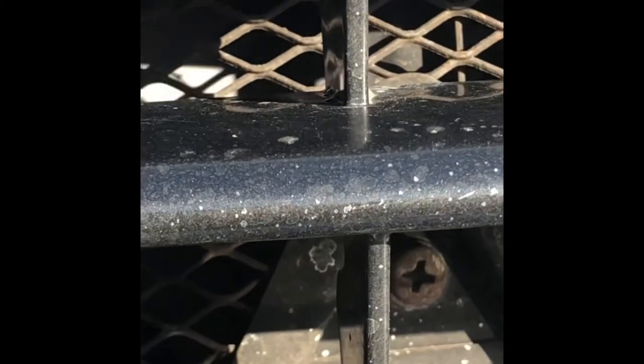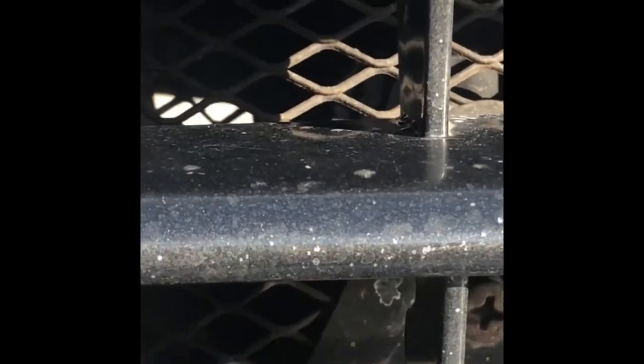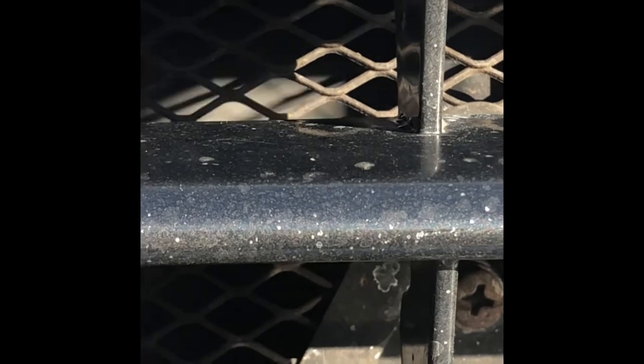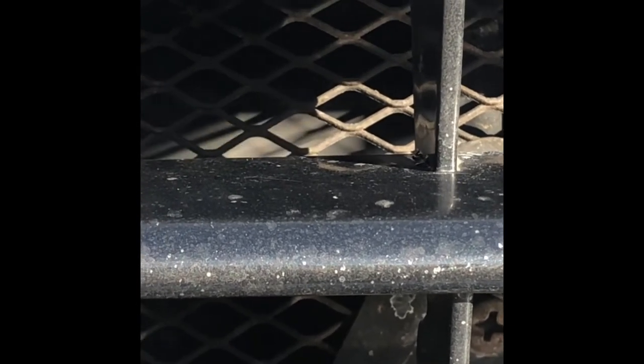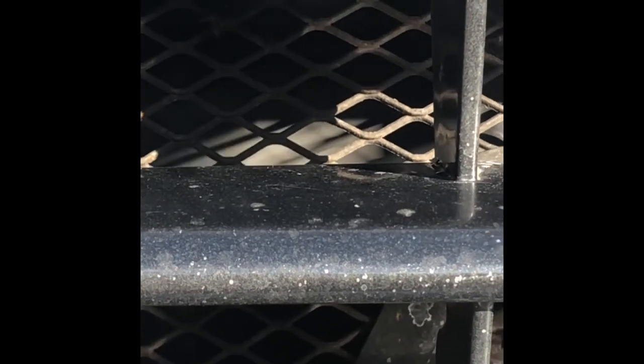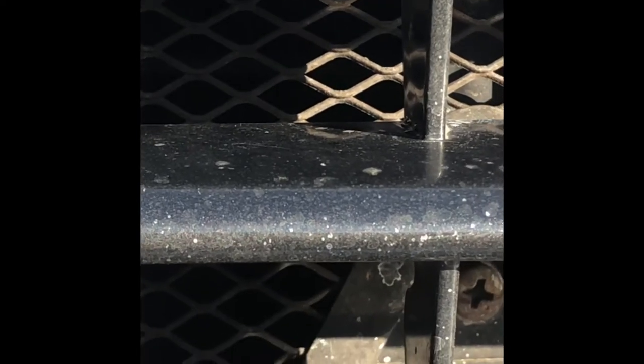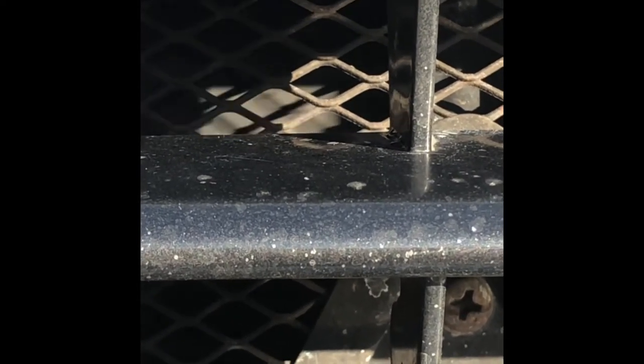Here's the cooling fan where the condenser is located. It stops spinning, and once the compressor kicks in, that turns on. Then it turns off, and it gets back in — cycling in sync with the compressor.